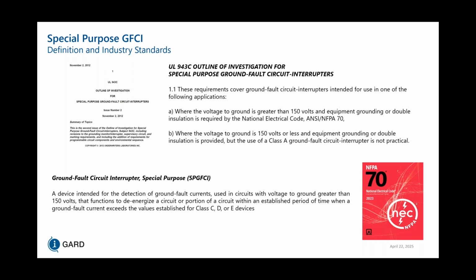So ground fault circuit interrupters, there's a special purpose GFCI or SPGFCI, and it's a device intended for the detection of ground fault currents used in circuits with voltage to ground greater than 150 volts that functions to de-energize a circuit or portion of a circuit within an established period of time when a ground fault current exceeds the values established for Class C, D, or E devices. So in this presentation, we're going to take you through what Class A, and what Class C, D, and E devices look like and what the decision-making tree looks like to determine which one you would require.